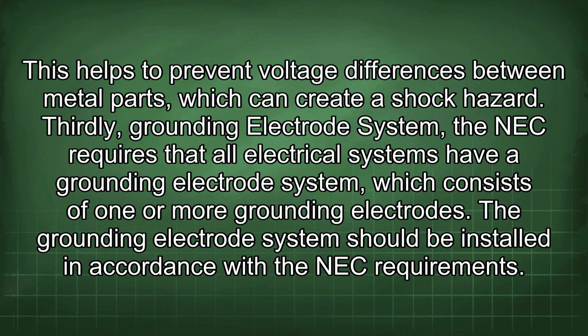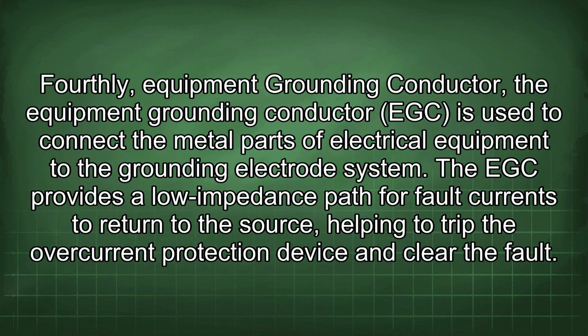Thirdly, grounding electrode system. The NEC requires that all electrical systems have a grounding electrode system, which consists of one or more grounding electrodes. The grounding electrode system should be installed in accordance with the NEC requirements. Fourthly, equipment grounding conductor. The equipment grounding conductor, EGC, is used to connect the metal parts of electrical equipment to the grounding electrode system. The EGC provides a low impedance path for fault currents to return to the source, helping to trip the overcurrent protection device and clear the fault.